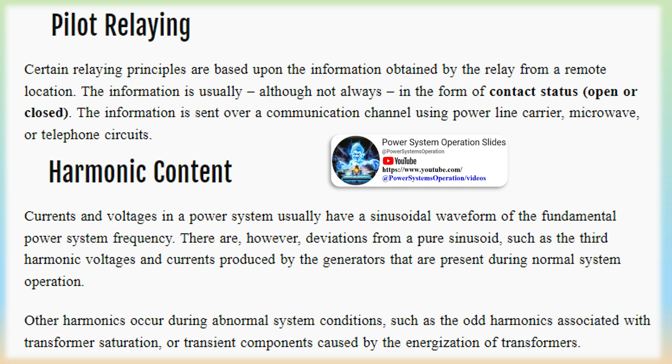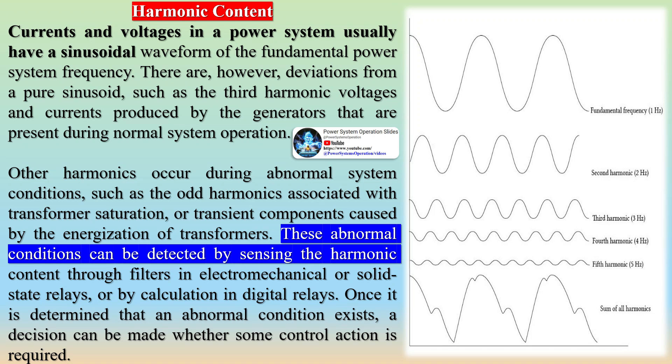Other harmonics occur during abnormal system conditions, such as the odd harmonics associated with transformer saturation, or transient components caused by the energization of transformers.